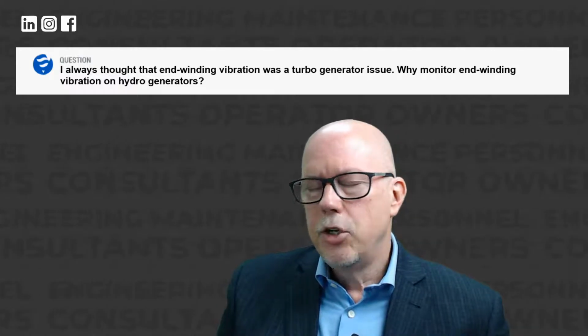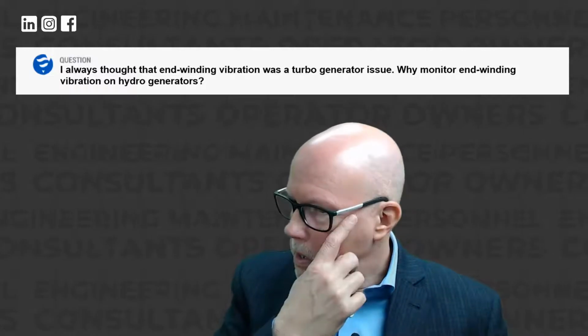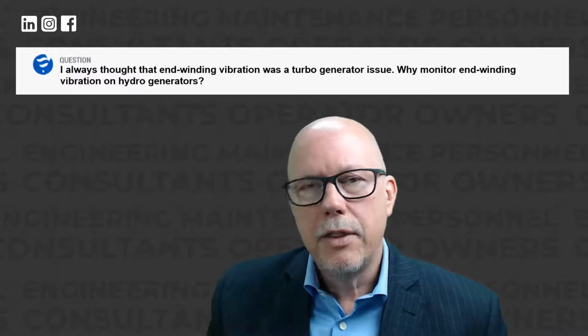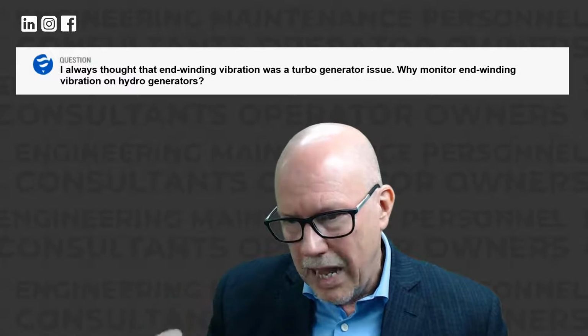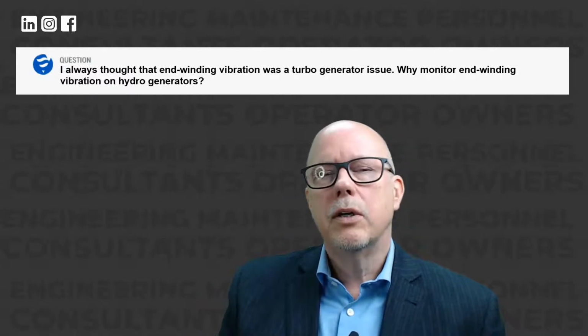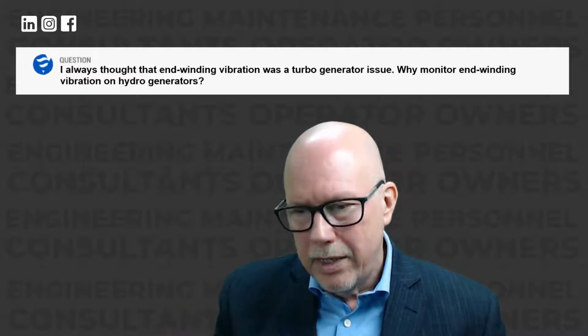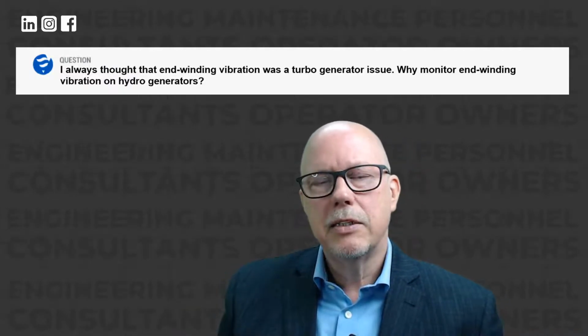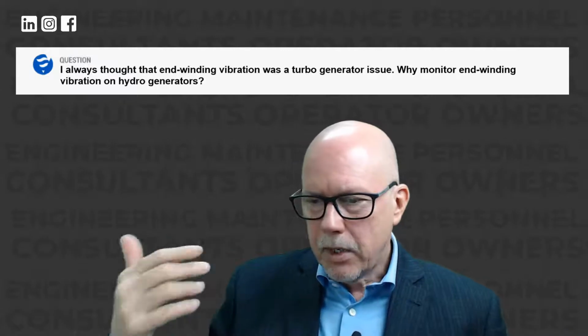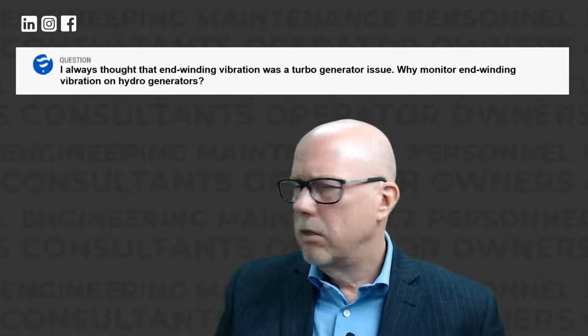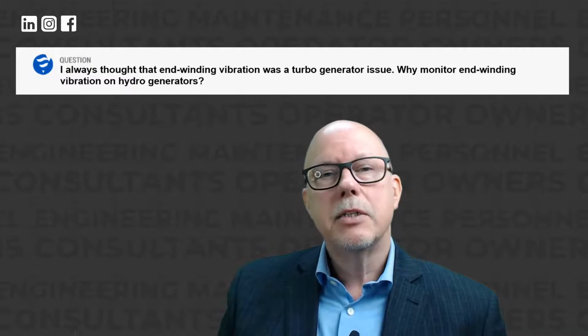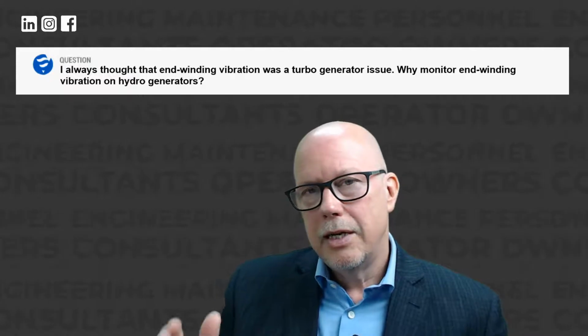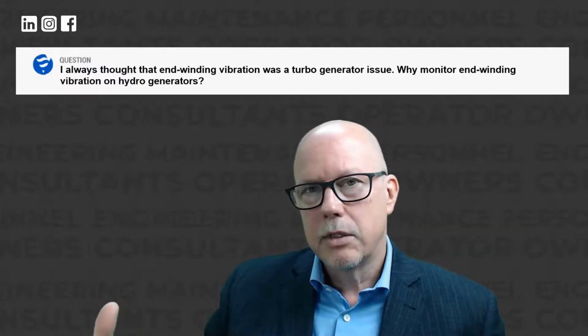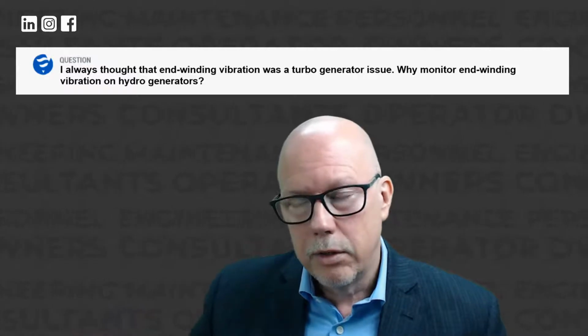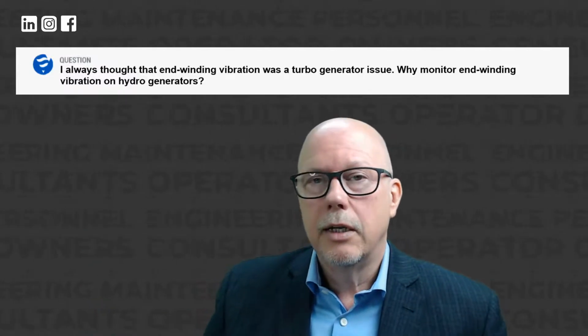And they used this stoppage, this outage, to go in there and stiffen the windings, add support blocks, remove ties and put in new ones, using the wet ties, which are much better to hold the windings in place. They did a lot of work. When the unit was restarted, I believe three weeks or a month later, they were very happy to see that the vibration had decreased significantly. But they were also very surprised to see that adjacent windings on which they had sensors, but had not worked on, also showed reductions in vibration.